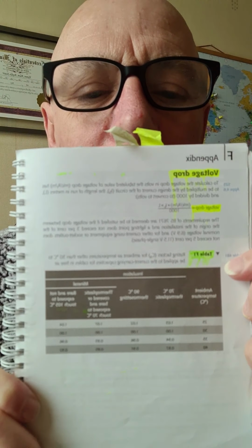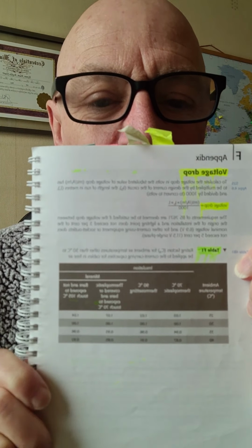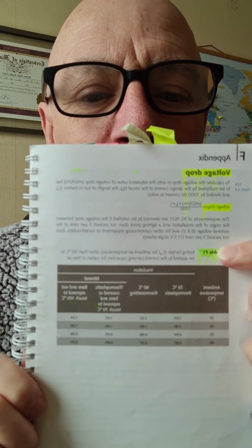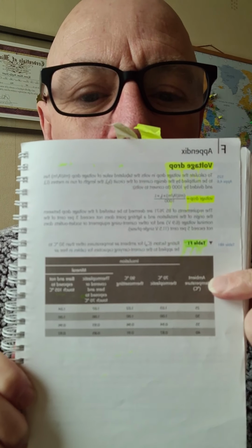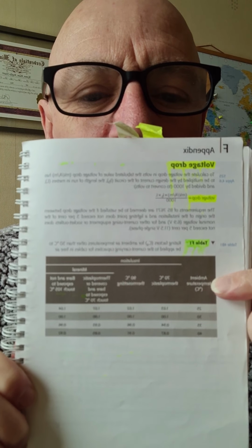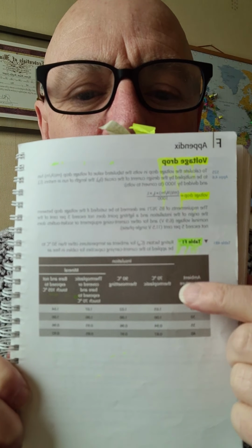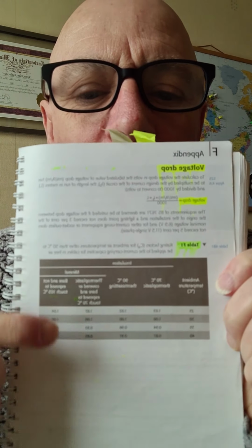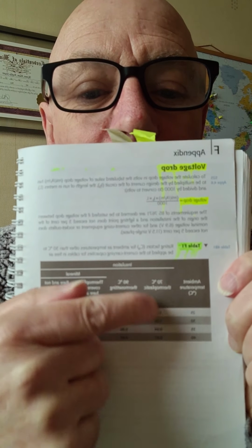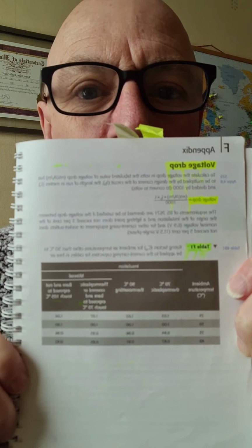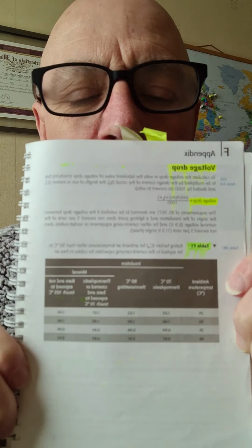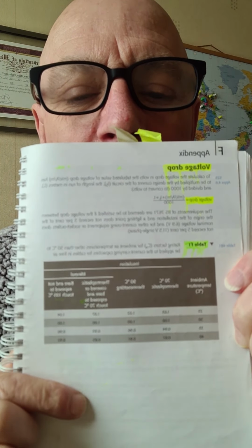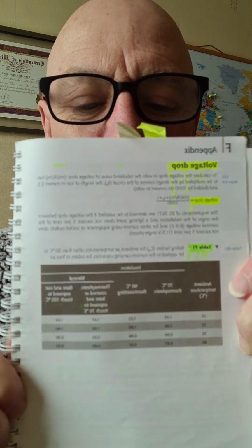Then if we're looking at the ambient temperature surrounding the cable, so that might be the temperature in the room, then we've got table F1, which is for ambient temperature. Important thing to note here is there's a differentiation between thermoplastic and thermosetting cables as well, so they're quite useful. Again, this is quite limited compared with the main regs book. It only goes up to a certain amount of degrees. If you've got higher than those degrees, you'd need to refer to BS 7671.